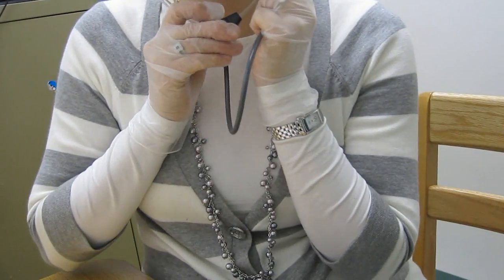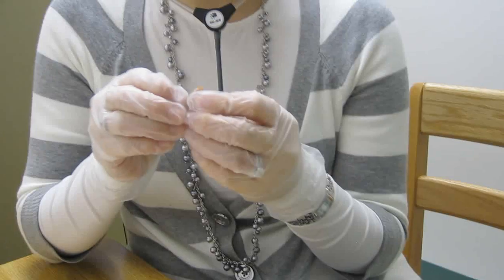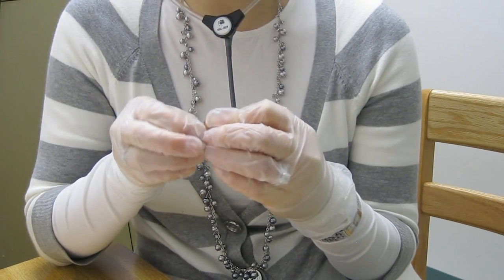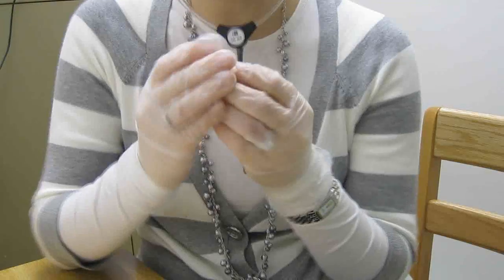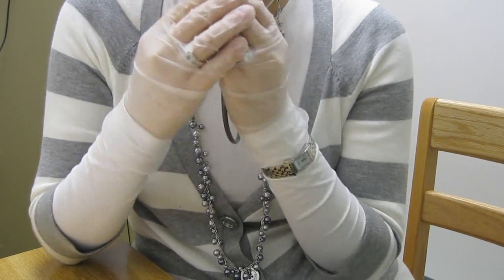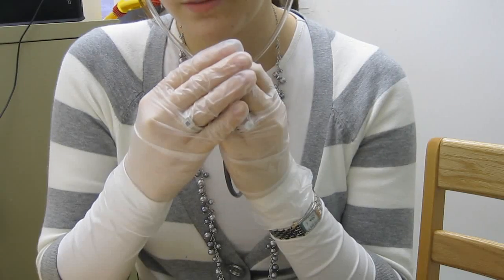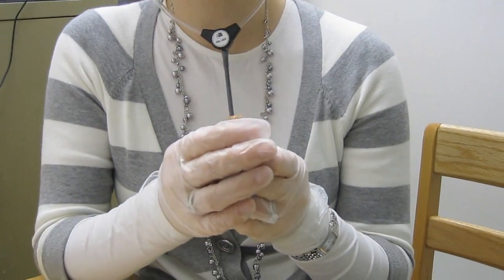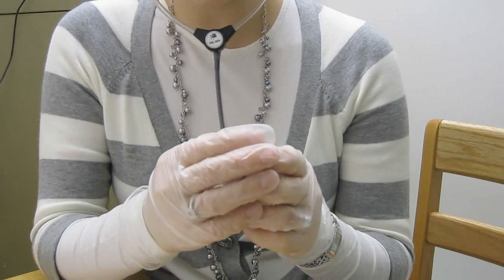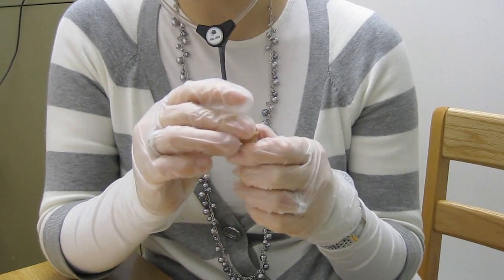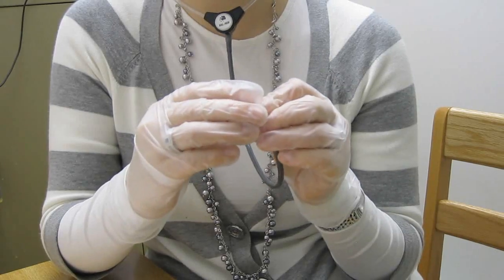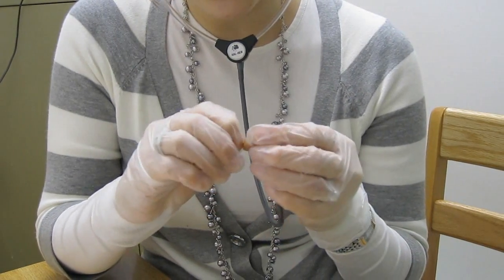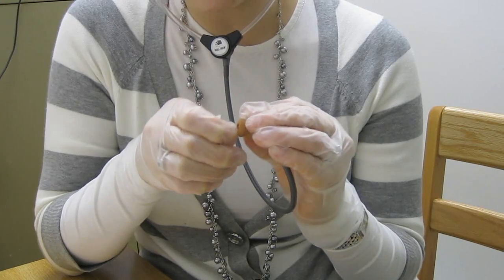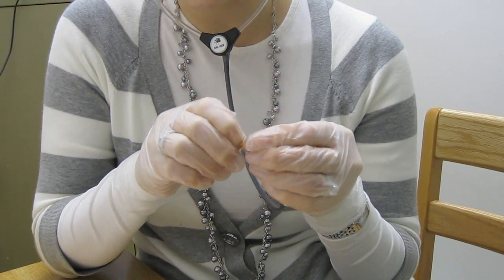Hi, now we're going to check this in-the-ear hearing aid to make sure that it's working properly. We're going to do a listening check. So we make sure that the hearing aid is turned on, which it is because we closed the battery door. And we're going to say the 6 Ling sounds to see if we hear them properly. Ooh, ah, ee, sh. Sound is clear, there's no distortions, there's no static, there's no hum. The signal does not cut in and out, not either when you press on the case or if you move the hearing aid around. The volume control works fine. If you turn the volume control wheel, it gets louder or lower and does move easily.